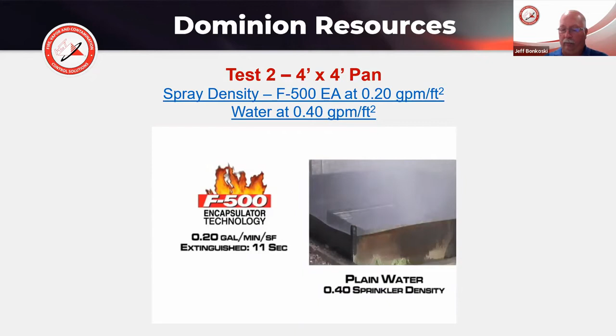Fire's out. Okay, so here's just an example. At a sprinkler density of 0.2 with a class B liquid, F500 at 3% was able to extinguish that fire in 11 seconds. At 0.2 gallons per minute per square foot, we're at 0.40 gallons per minute per square foot. It took it 30 seconds.